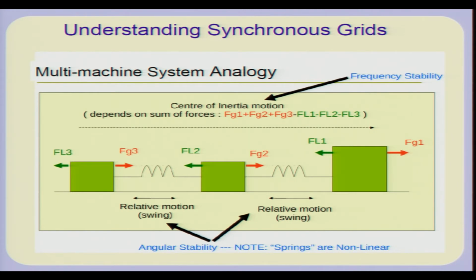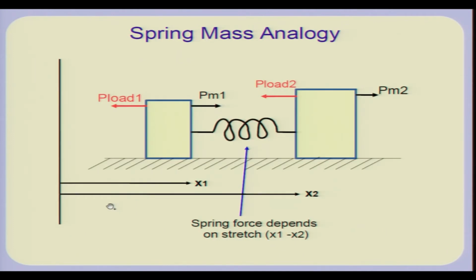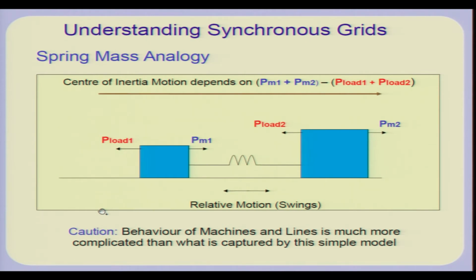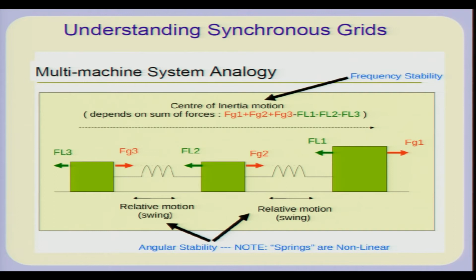That can happen. You also have a kind of swing, because if there is any disturbance the rotors tend to oscillate with respect to each other, again seen in this two mass spring system. The important difference between a two machine system and a three machine system is that now there could be many patterns of relative motion. For example, if you have a large mass and two small masses connected by a stiff spring and a weak spring, you can have the two masses swinging together with respect to the large mass, or you could have the two masses swinging against each other. So you can have various patterns.